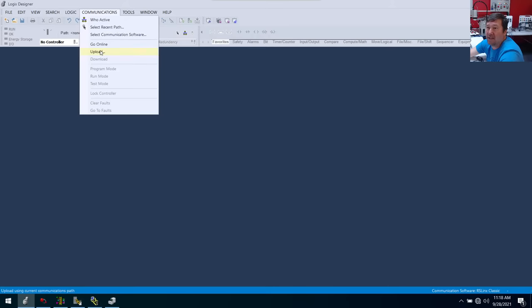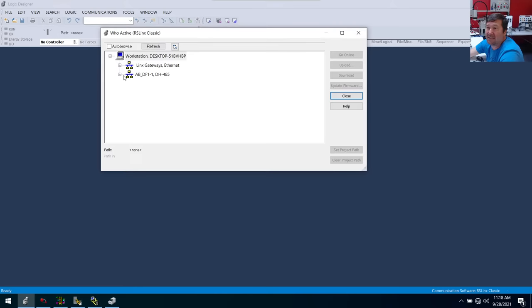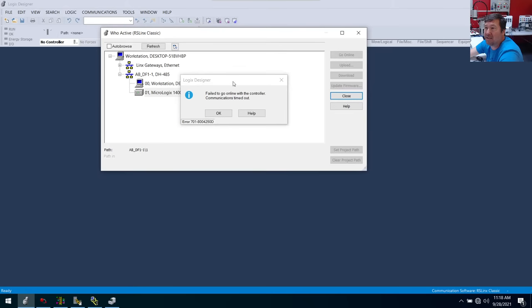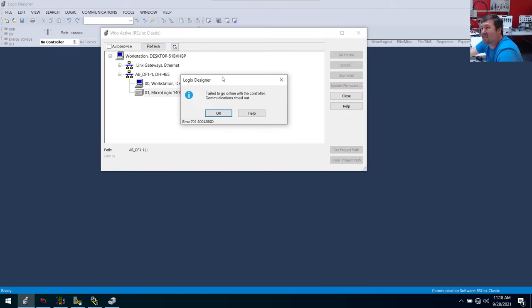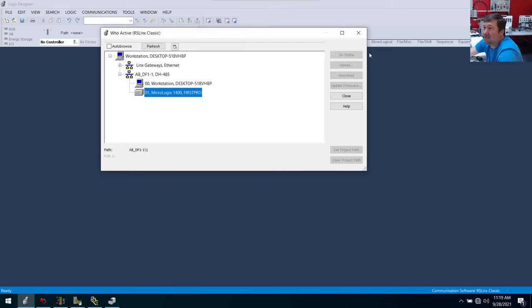Now I'm going to go to Communications. We have Go Online, Upload, and Download here. I always like to go to Who Active — I can make sure that I have the right PLC. We click Serial, and there is our MicroLogix. And it says failed to go online with controller — communications timed out — which is going to sound like we have an issue with our communications. I kind of wish they would massage this to say, hey, you've got an old PLC and new software. A lot of people will be like, I keep getting this error — this error means that you have the wrong software.